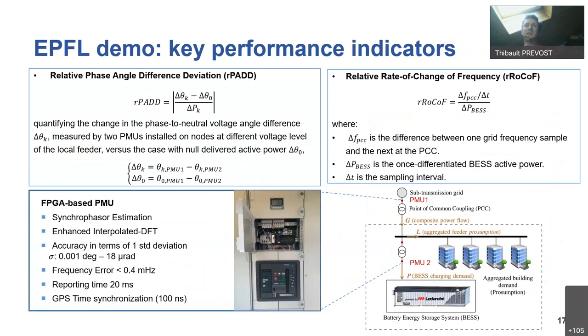Another interesting part is the key performance indicators. As we said, we want to define and test the grid forming without knowing what's in the control. So they developed two kinds of indicators. One is a relative phase angle difference deviation, and the other one is a relative rate of change of frequency. I think the relative rate of change of frequency is the easiest one to understand. And in fact, we'll see that the results are very easy to understand too. They were based on measurements from an FPGA PMU. So it's a commercially available PMU. It's a very accurate one, but commercially available.